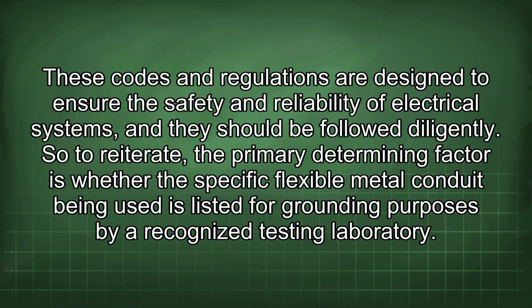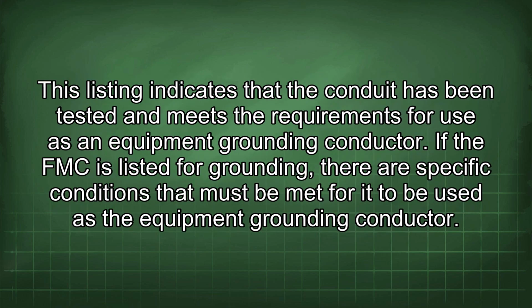So to reiterate, the primary determining factor is whether the specific flexible metal conduit being used is listed for grounding purposes by a recognized testing laboratory. This listing indicates that the conduit has been tested and meets the requirements for use as an equipment grounding conductor. If the FMC is listed for grounding, there are specific conditions that must be met for it to be used as the equipment grounding conductor.